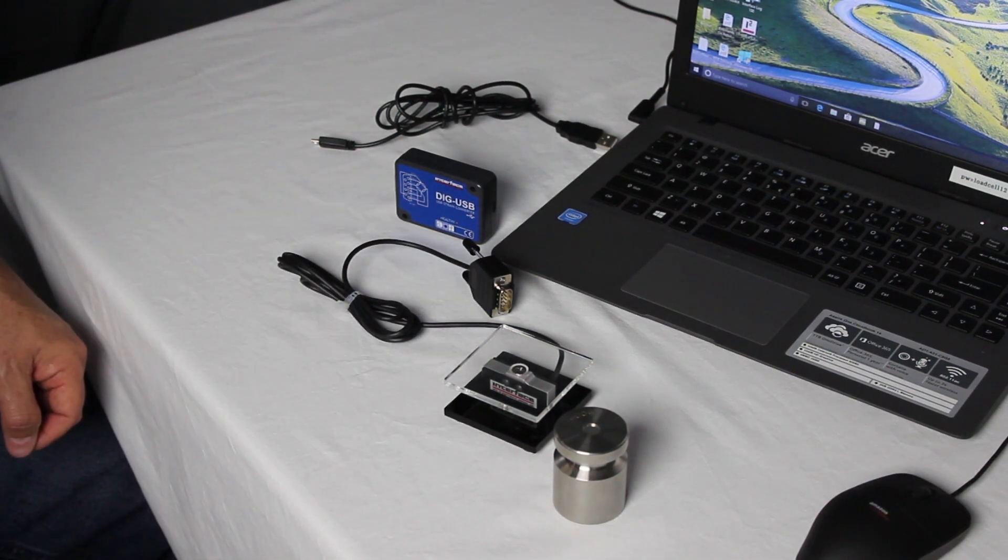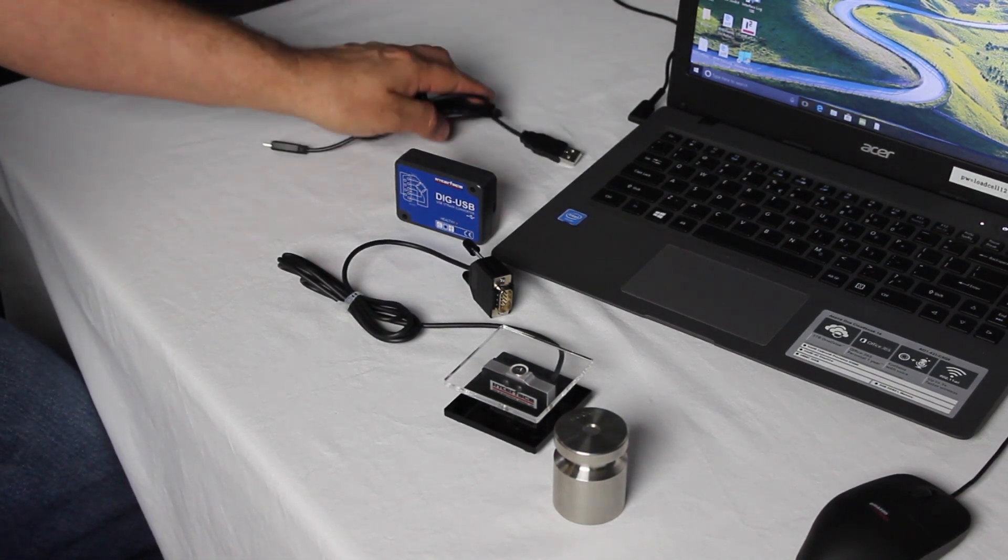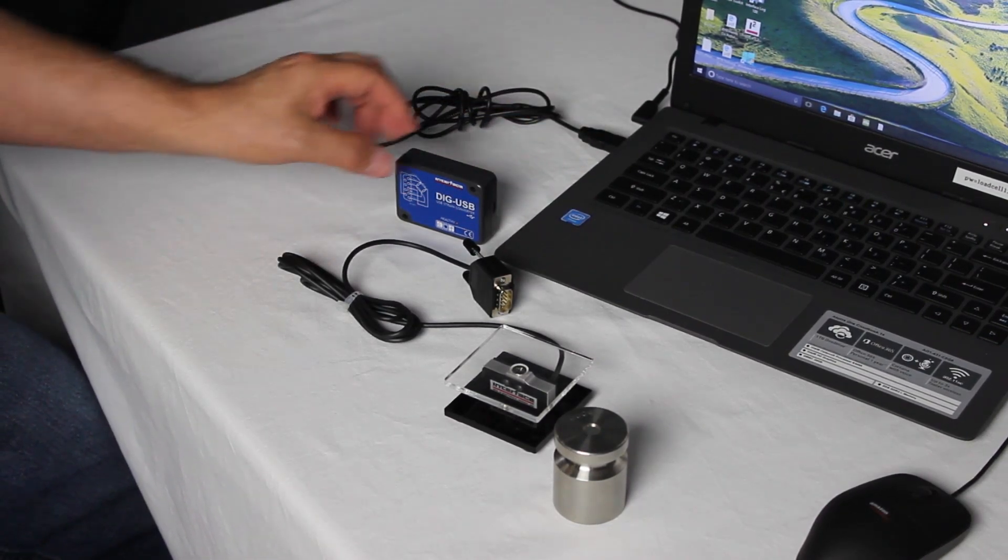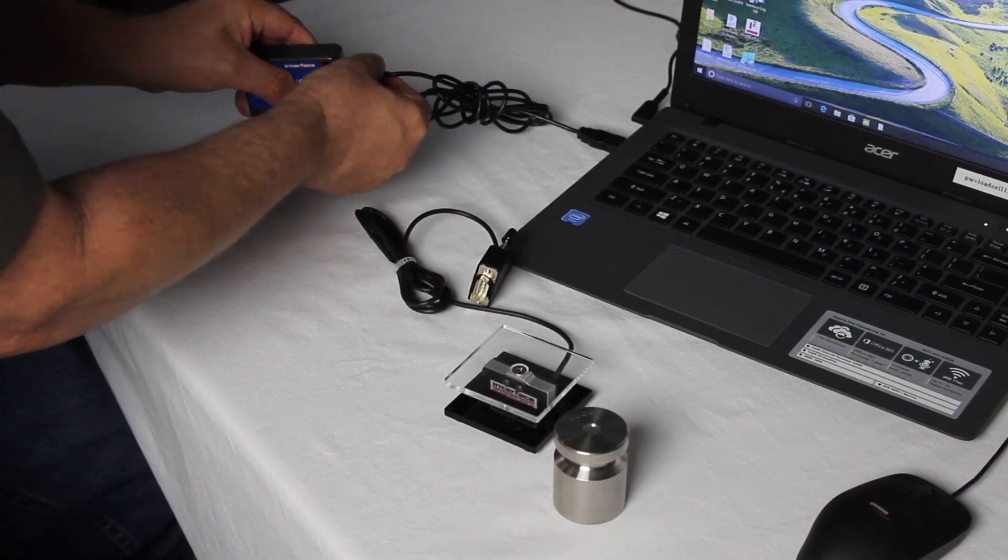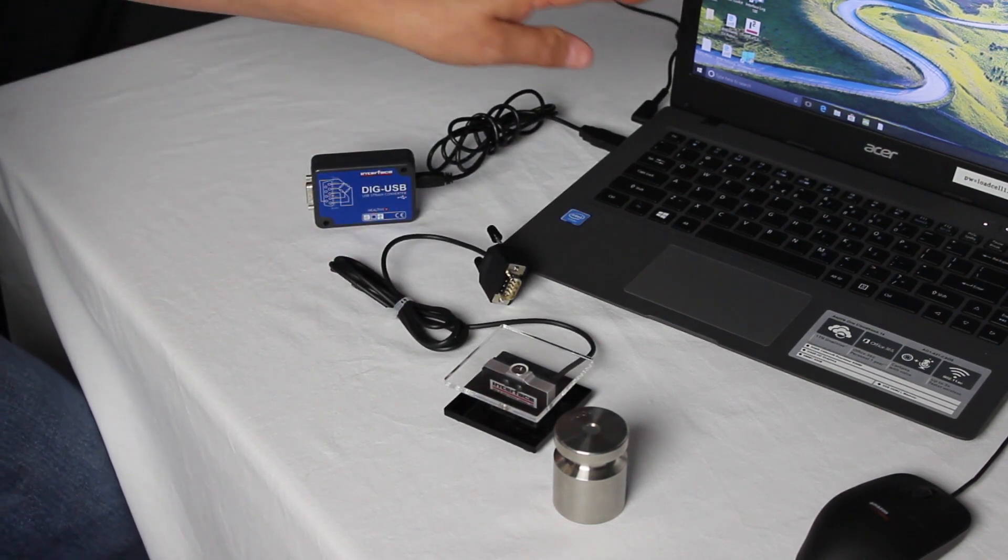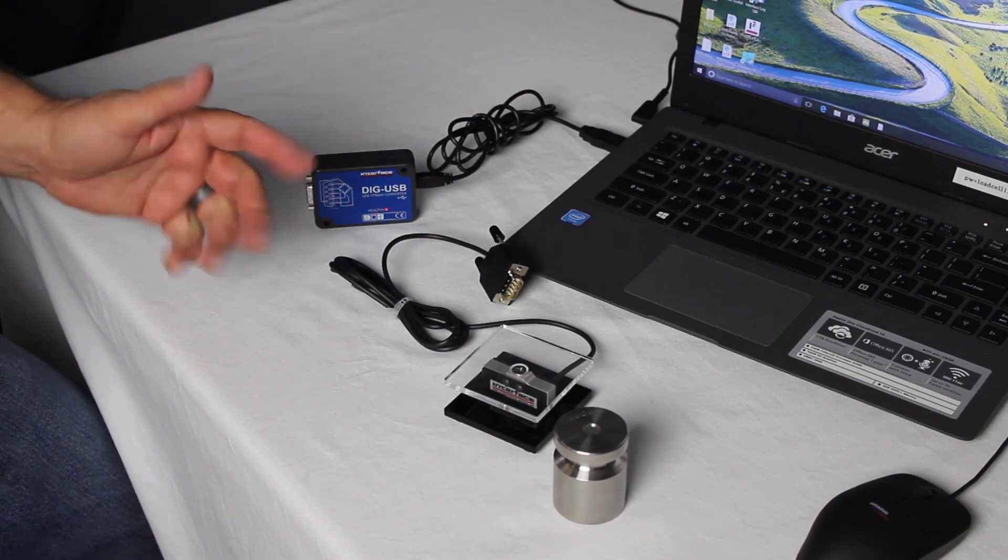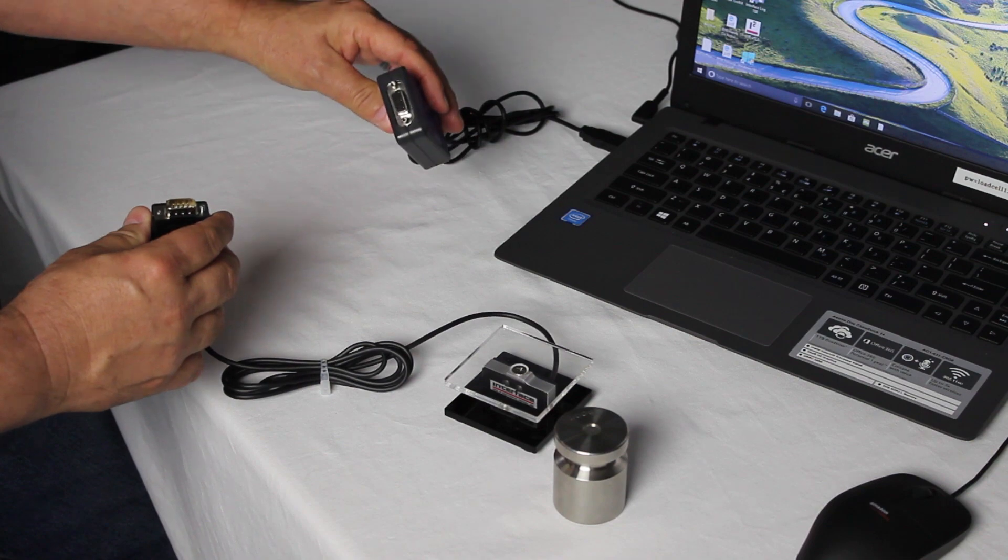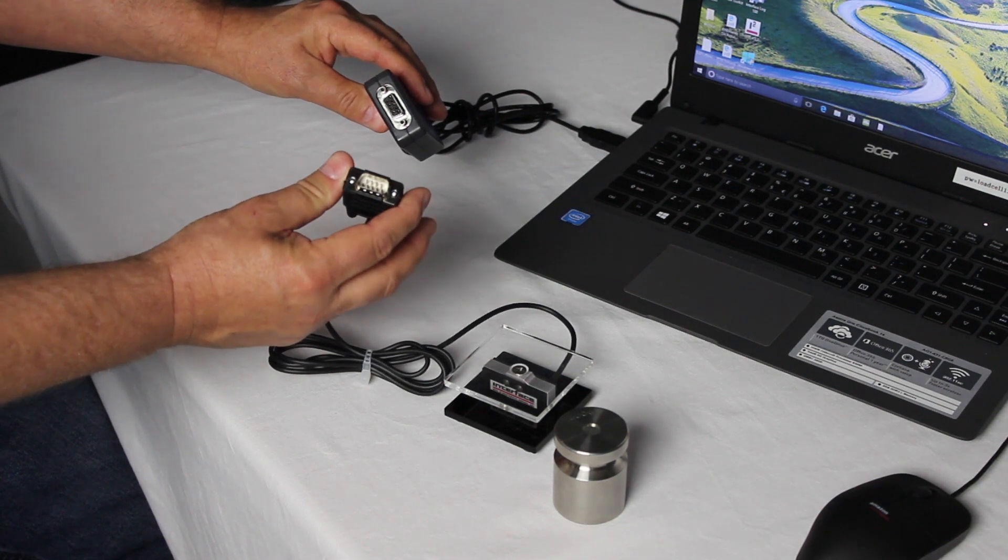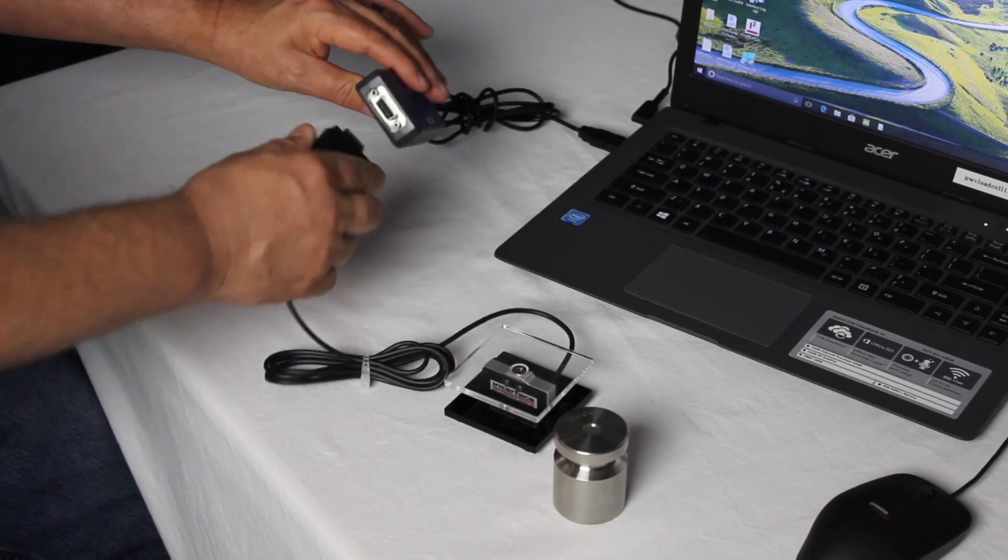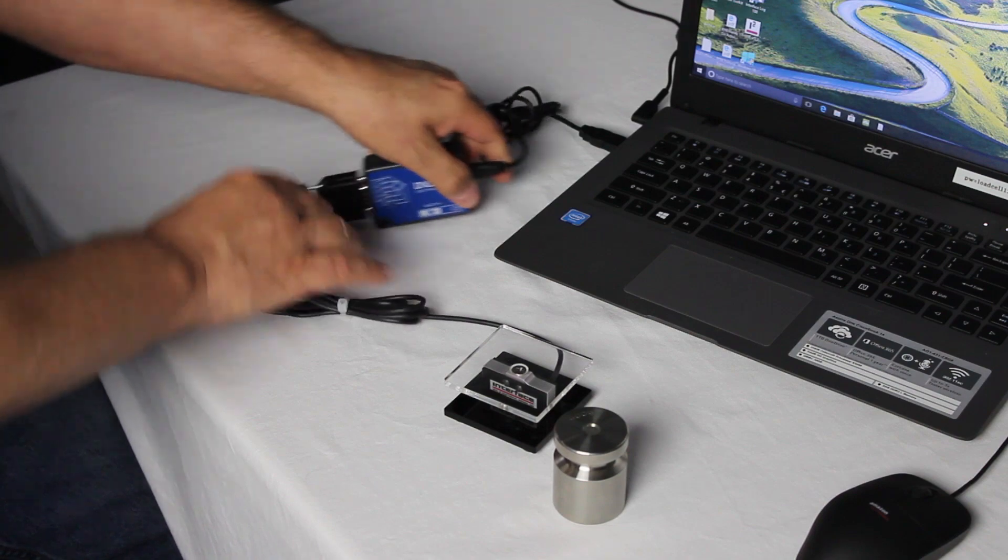After your software successfully loaded onto the PC, now we can connect the hardware. First we're going to start with the USB to micro USB cable. We're going to plug the USB side into the PC. And then the micro USB side, we're going to plug it into the DIG USB module. We're going to wait until the hardware successfully installs onto the computer. This should be automatic. Next, we will connect the load cell to the DIG USB. Notice that the DIG USB has a 9-pin D-type connector female. So you'll need a 9-pin D-type connector male installed onto your load cell. We connect the two together. And now the hardware is connected.